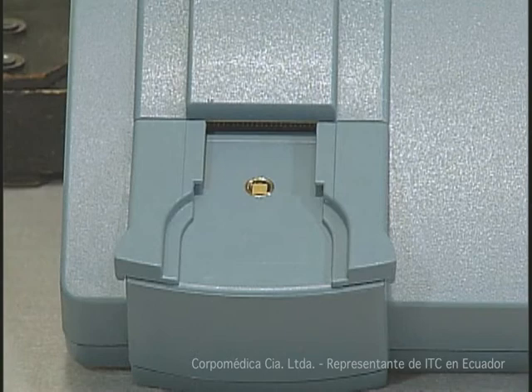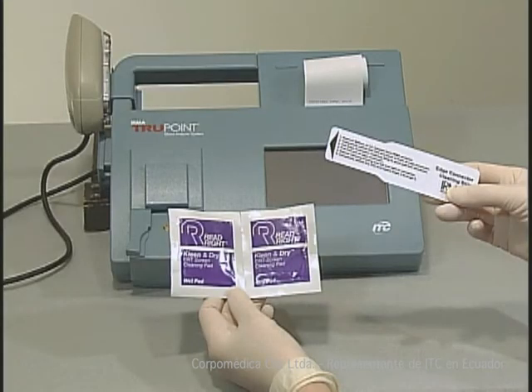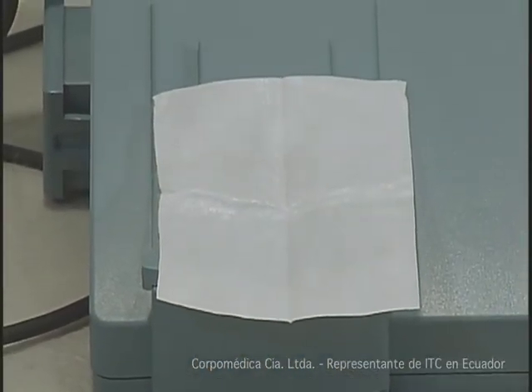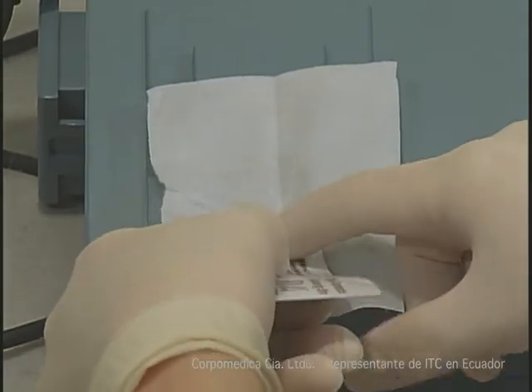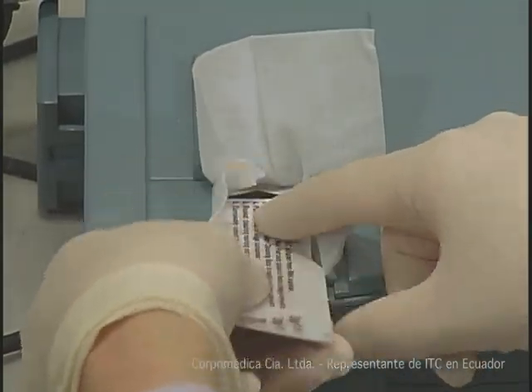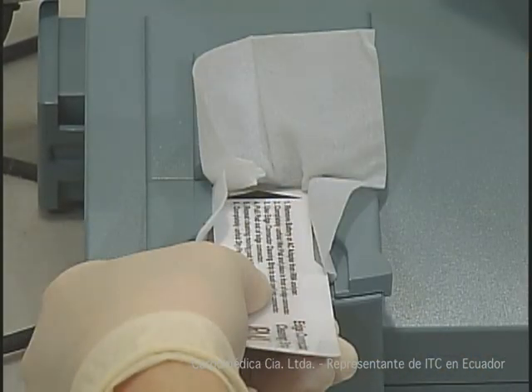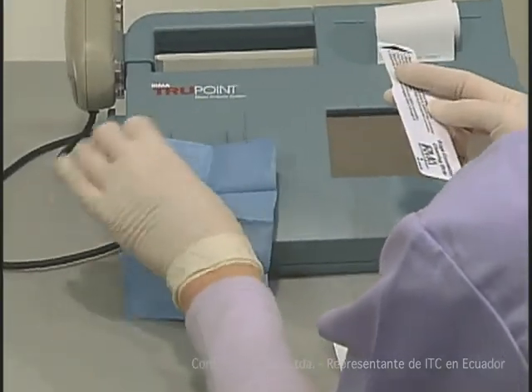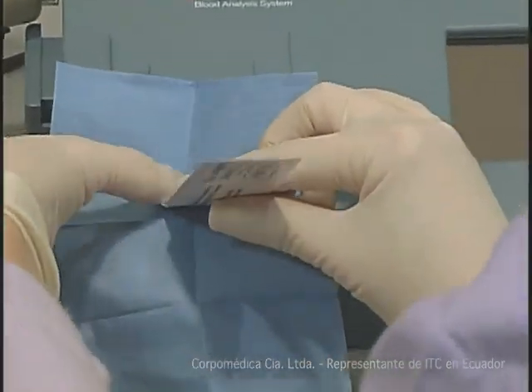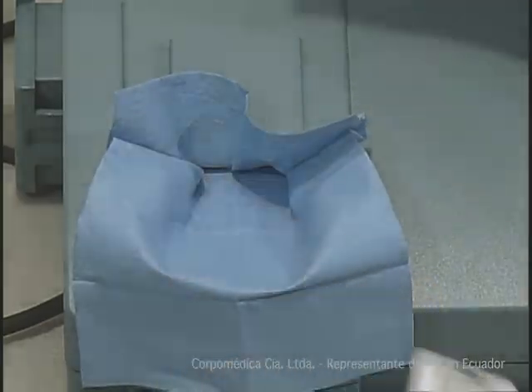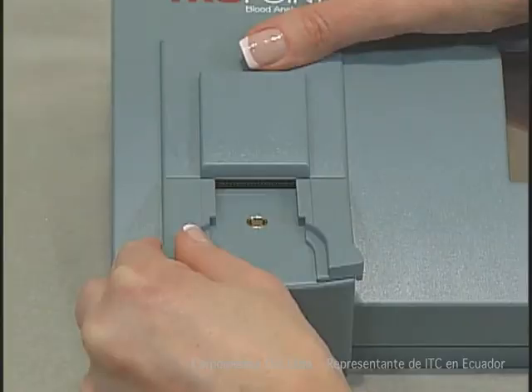Clean the edge connector if it is accidentally contaminated, or when the electronic quality control, temperature test, or sensor error codes indicate contamination. To use the ITC edge connector cleaning kit, remove the battery or AC adapter from the analyzer. Place the wet pad in front of the edge connector. Use the edge connector cleaning strip to push the pad into the edge connector, moving the strip and pad left and right. Then, place the blue dry pad in front of the edge connector and repeat the process.